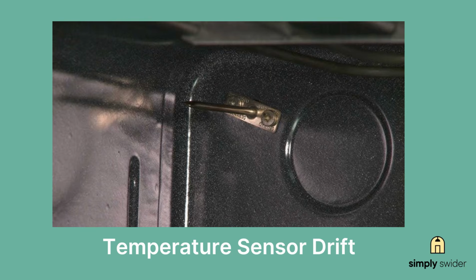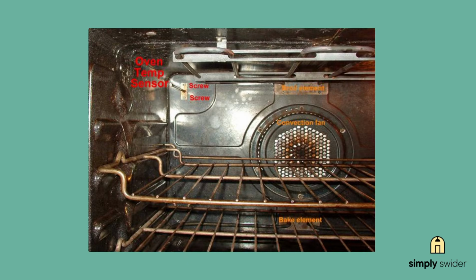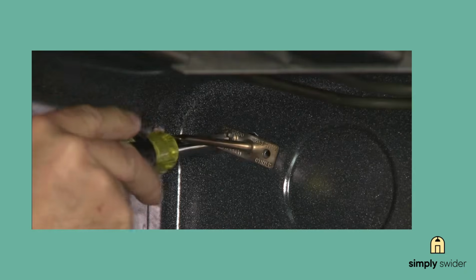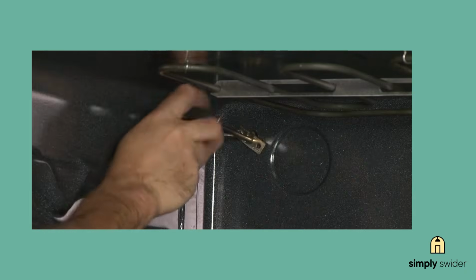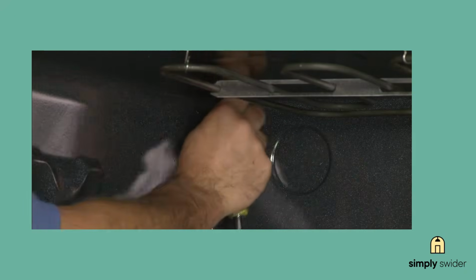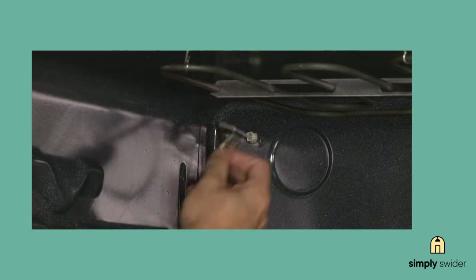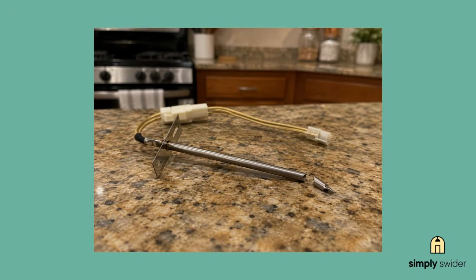What's happening is that the RTD sensor's resistance has drifted out of calibration, usually from moisture getting into the probe or just internal component degradation. Here's what you're going to do. Test the sensor resistance with your multimeter at room temperature. At 70 degrees, you should see about 1080 ohms, give or take about 5 ohms. If it's way off from that range, the sensor's done.